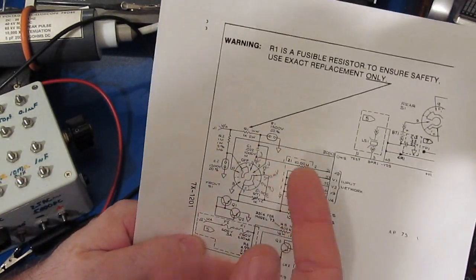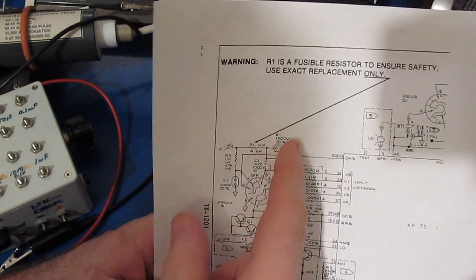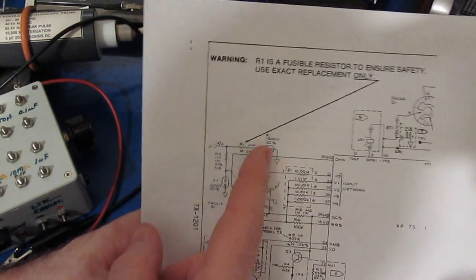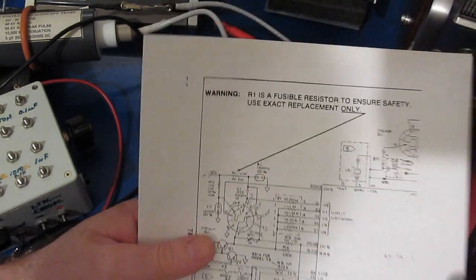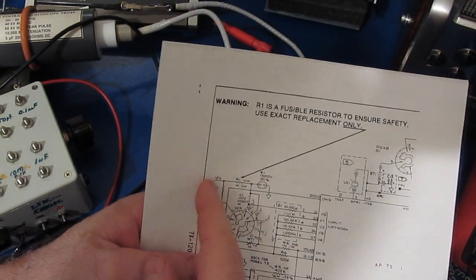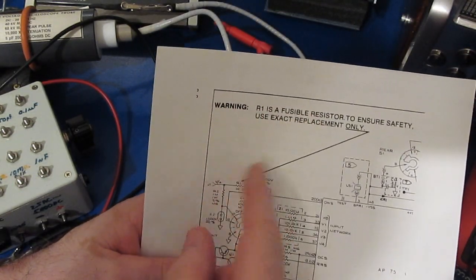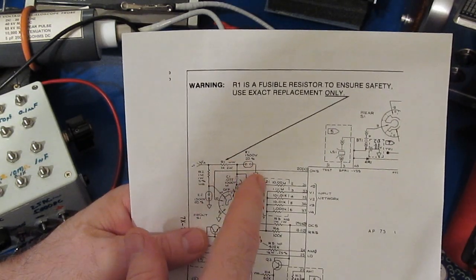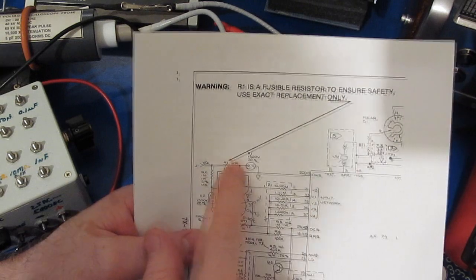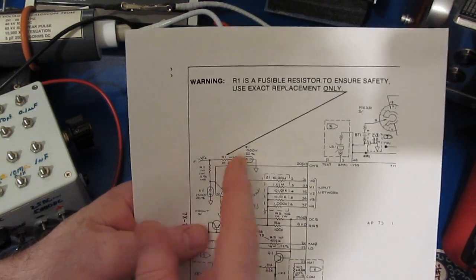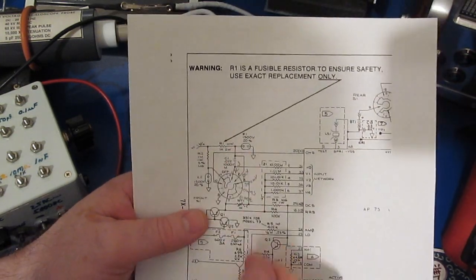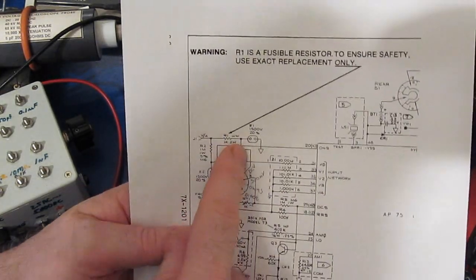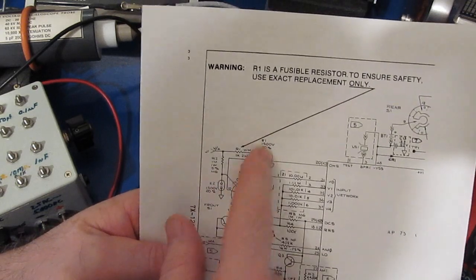I don't know if that would have made it any more robust or not, but that's typically how other meters are protected. The fact that this is a spark gap versus a MOV, I wasn't too concerned about that. Obviously with the MOV it's just going to clamp the voltage at some level, where the spark gap once it arcs over you basically end up with a very low impedance path to ground. And so the voltage at this point here basically becomes zero volts once this thing arcs versus with the MOV it would have to sustain whatever voltage that is.